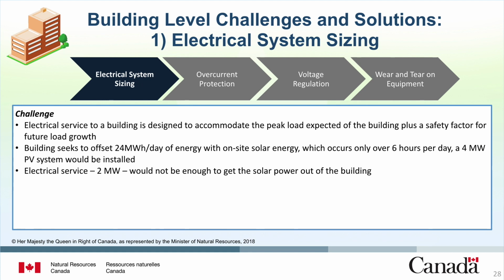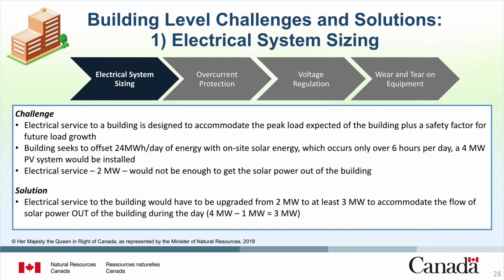and the electrical service, 2 megawatts, would not be sufficient to get the solar power out of the building. A solution would be to have the electric service to the building upgraded from 2 megawatts to at least 3 megawatts to accommodate the flow of solar power out of the building during the day. 4 megawatts minus 1 megawatt equals 3 megawatts.